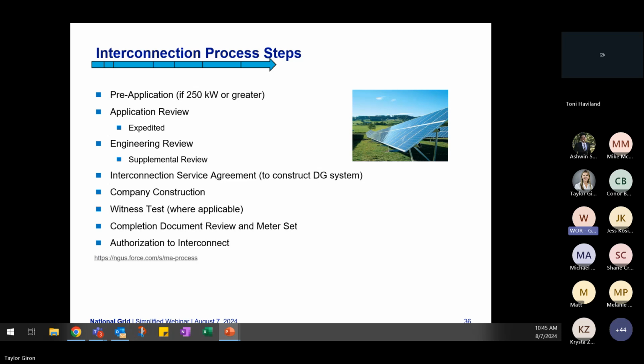If construction is required, we have a signed ISA. If payments were required and have been made, we then do our construction in the field. Once you're at the point of the COC process - this is usually on residential property, residential services - we will not do any witness testing. We use the commissioning memo process as part of the COC process to then issue the new meter exchange, and then we will send you the ATI.